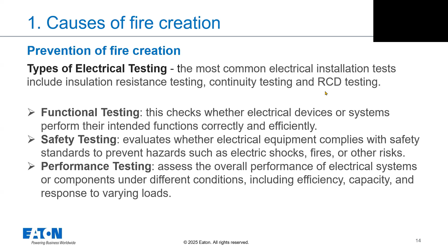To link this to standards for installations, I'd like to mention the IEC standard. The old version was 61, but now we have one common version, 60364-6, which contains two levels: initial verification and periodical verification.